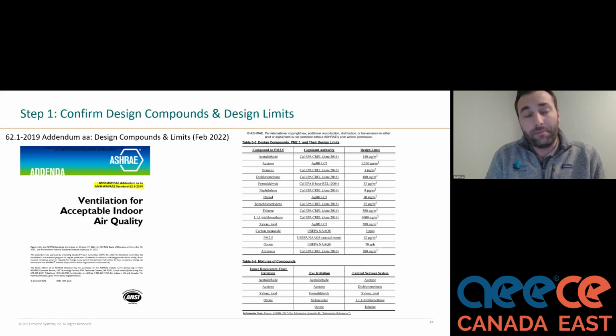So you want to select a product that definitely doesn't produce ozone, but you also want to select one that can remove ozone as well. Noticeably missing from this list is CO2. CO2 has traditionally had limits, for example, in the LEED pilot credit for IAQp, but CO2 is not a specific contaminant of concern where there is a called out design limit. Now, we can talk more about that, but there are ASHRAE position papers on what an acceptable limit of CO2 is within a space, and that's typically what organizations like ours plug into the IAQp calculator, is that specific design limit.